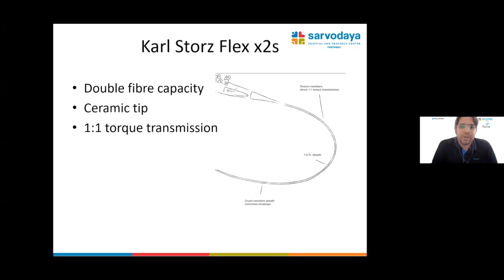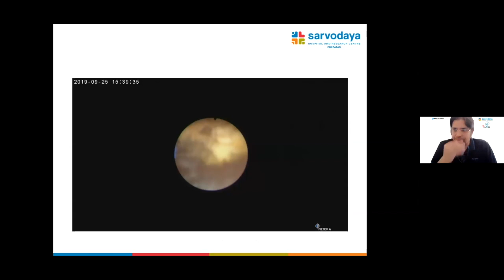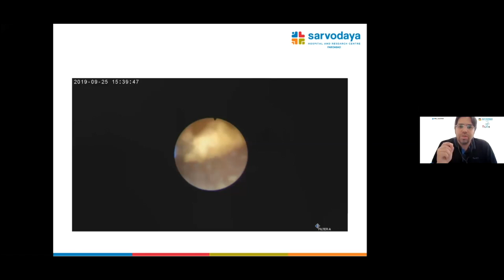Talking about the technical details, this also is a forward viewing scope with the 270-degree deflection on either side. The angle of view is 88 degrees. The working length is 67 centimeters, and the working channel is 3.6 French. And the sheath size is 7.5 French, and this is uniform compared to a P7 where it is tapering. So this is the image that we get with the FlexX 2S. We can see that it is very clear and we are not seeing any screen door effect. Of course, we have to slightly defocus in both these scopes to get a good image.